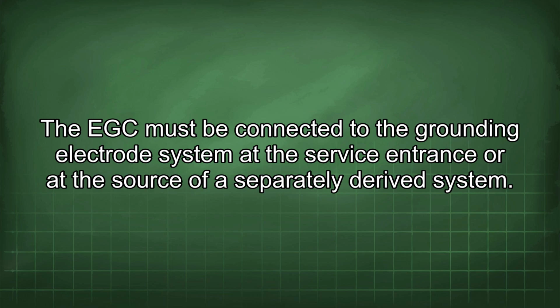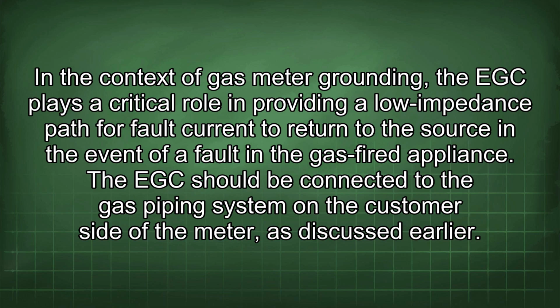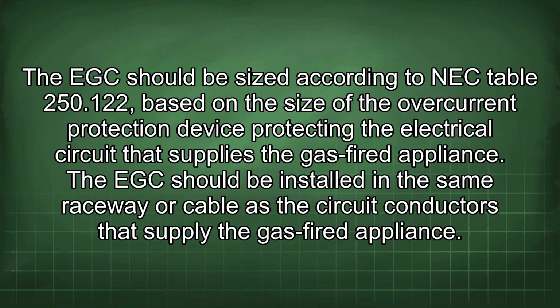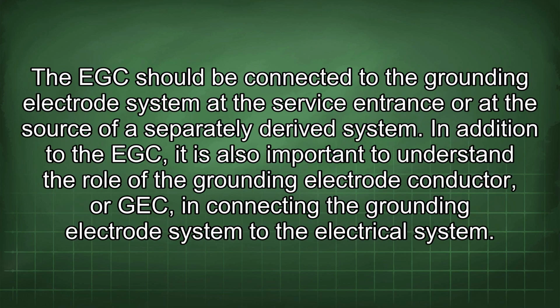a separately derived system. In the context of gas meter grounding, the EGC plays a critical role in providing a low impedance path for fault current to return to the source in the event of a fault in the gas-fired appliance. The EGC should be connected to the gas piping system on the customer side of the meter, as discussed earlier. The EGC should be sized according to NEC Table 250.122, based on the size of the overcurrent protection device protecting the electrical circuit that supplies the gas-fired appliance. The EGC should be installed in the same raceway or cable as the circuit conductors that supply the gas-fired appliance.